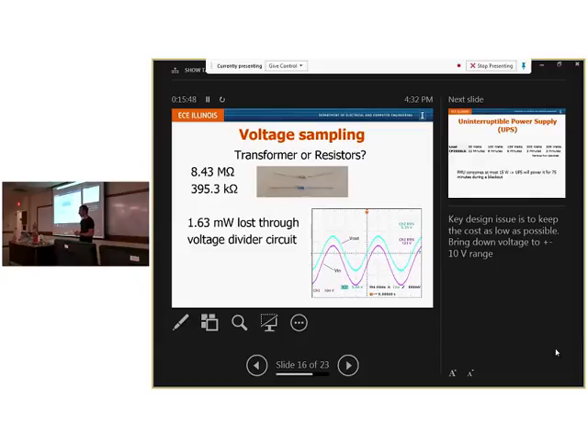in terms of device and better capability. Also, a side note on the PMUs, I was curious - there are two classes of PMUs, and I was questioning a fellow in Texas, Kuzunovic, who's from Serbia. I asked why there are two standards, and he said there were two legacy devices that we wanted to incorporate into a PMU, and we didn't want to have people rewrite their algorithms from those to have to build a PMU. So to me, that says there's an opportunity to rewrite the standard because you're not burdened by algorithms that somebody generated 20 years ago. So it's an opportunity.